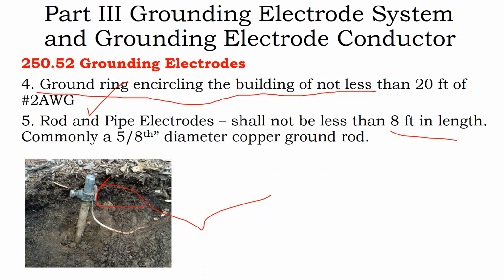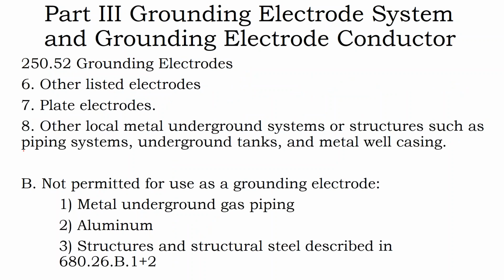That might not be as conductive as using a ground rod. And so if you can use a ground rod, you should, is the short of it. If you have the opportunity to put a ground rod there as your grounding electrode versus any other thing, it's only in the circumstances where, say, 3 feet down from your house is a concrete shelf that you can't bust through, so you have to make your own kind of ground ring or go away from the off-the-shelf parts into more homemade solutions. You don't want to be there as a starting point. You want to be there because you have no other options. Using a ground rod or a ground plate is the common way to do it. Because not always is that building going to be qualified as a grounding electrode.